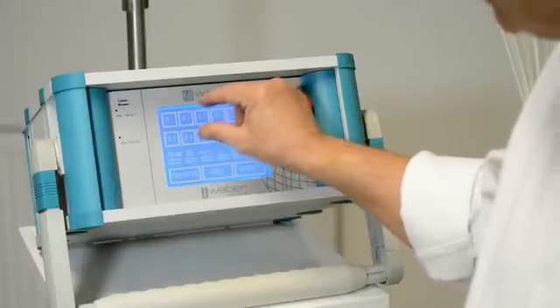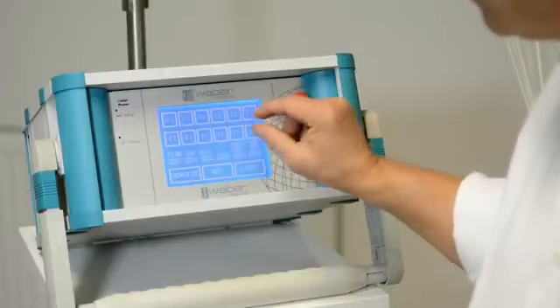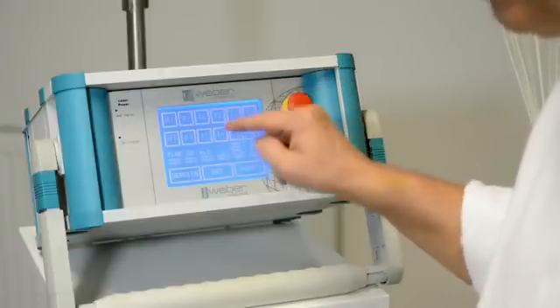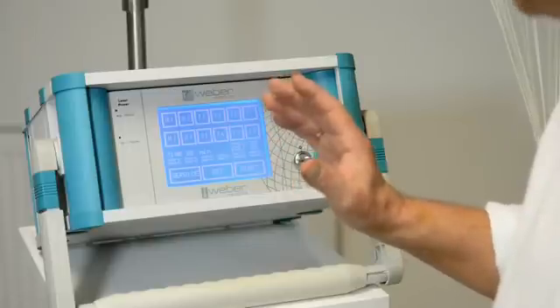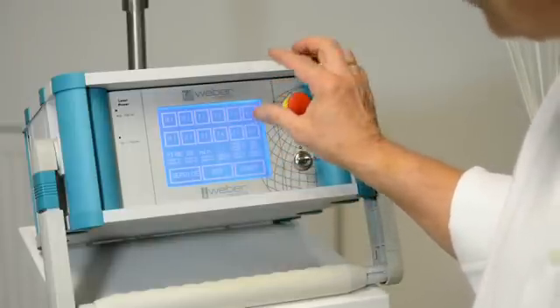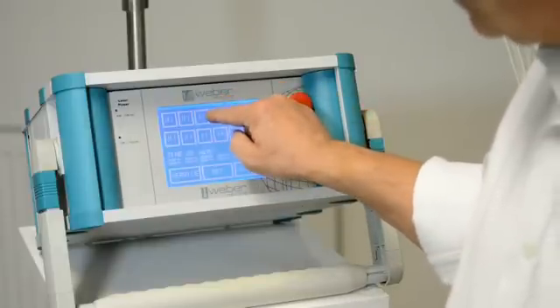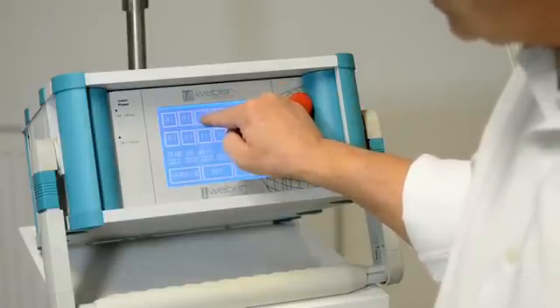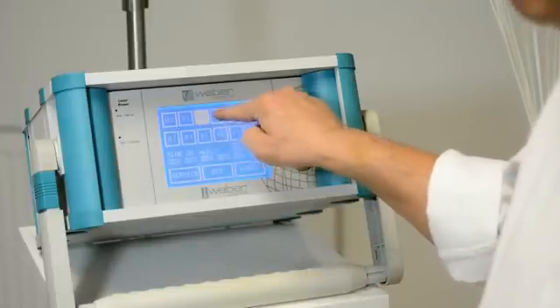In the basic setting, the device is running with 50% power and 20 minutes treatment time. If I want to change anything, I press the set button below, and with the set button I can change power of the lasers and the treatment time.